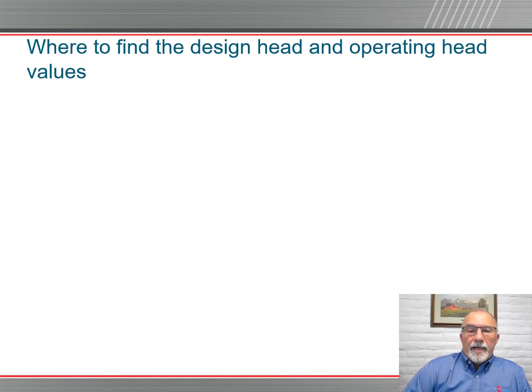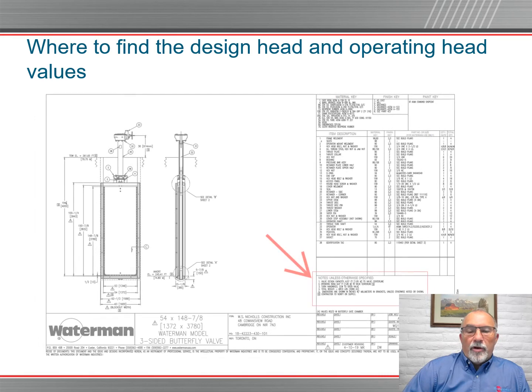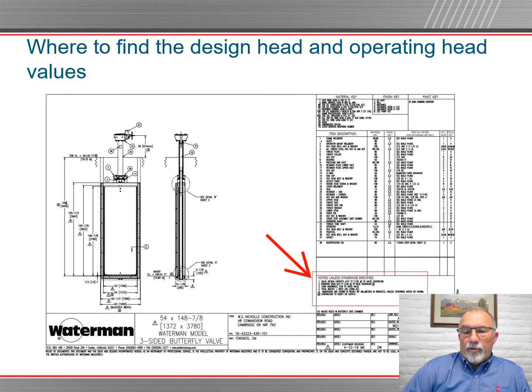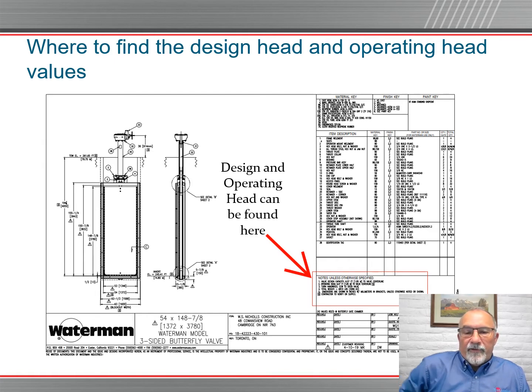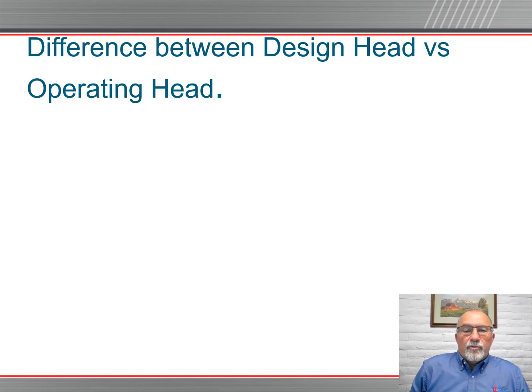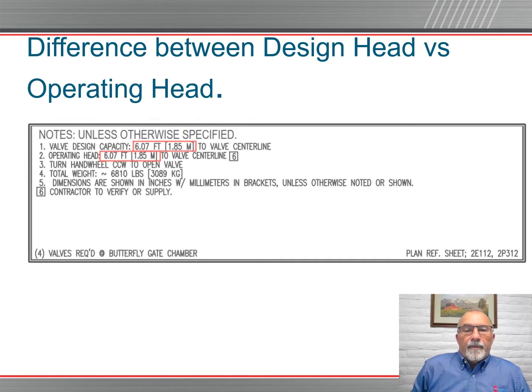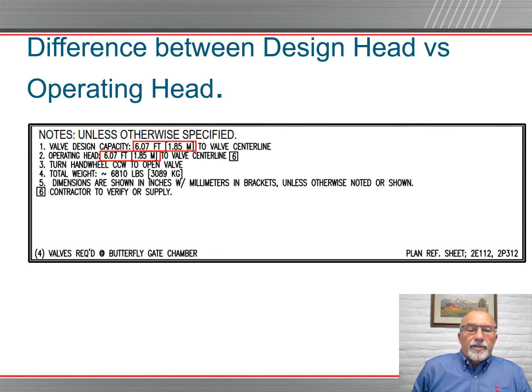Where you find the design head and operating head values, if you look at your drawing, they're found in the bottom right-hand corner in the notes section. Notes, unless otherwise specified, is how we talk about it. And we'll zoom in here. That's your design head, and operating head can be found in that area of the notes. This is what it looks like zoomed in. Notice in your job that we have a design capacity of 6 foot head, 1.85 meters, and of course the operating head is the same in this case.